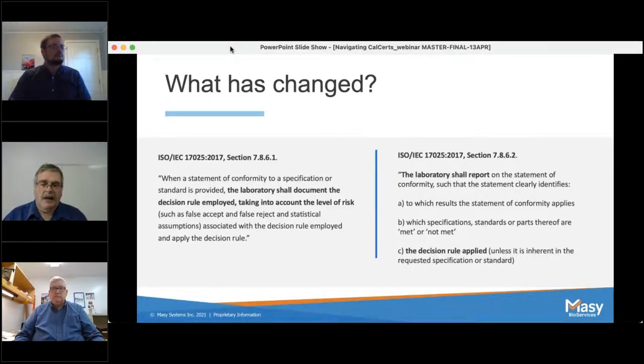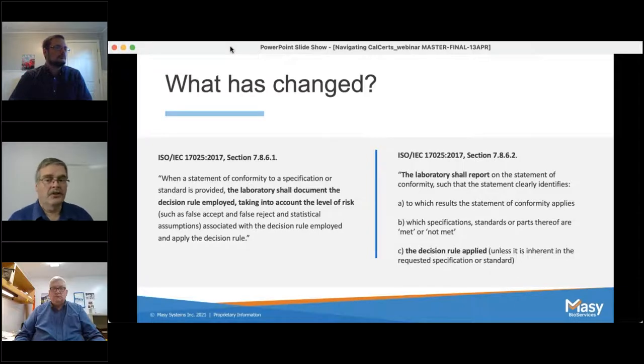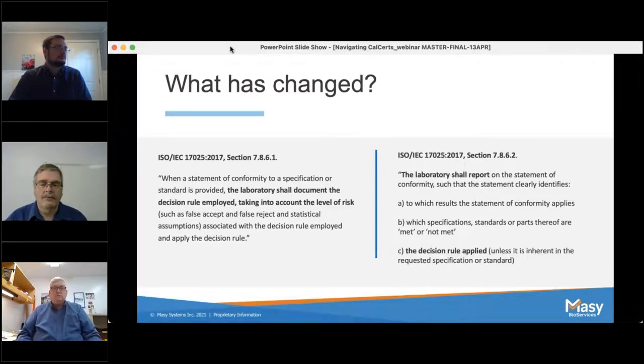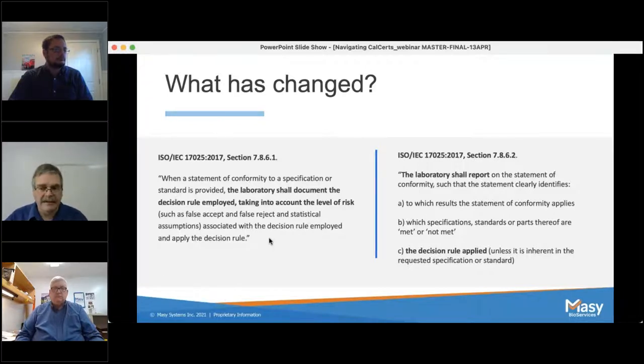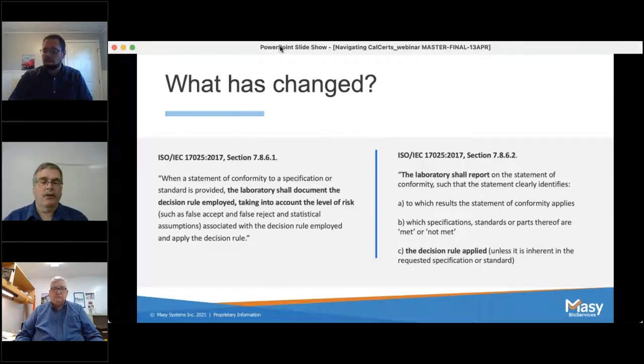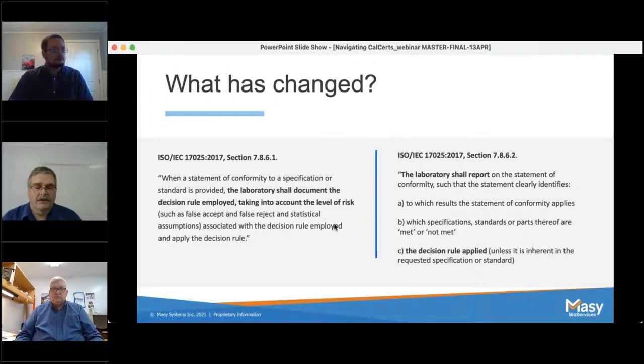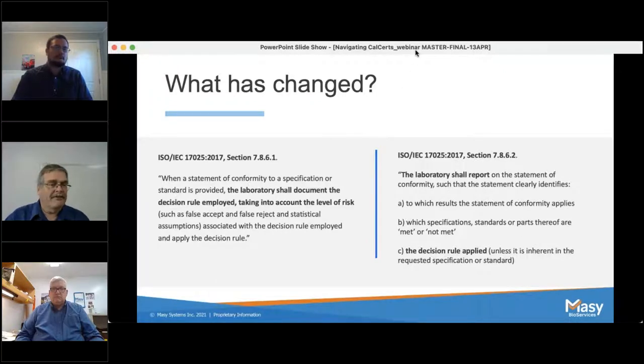So it went from a single sentence in the 2005 standard to referencing this decision rule in four different sections within the 2017 standard. These authors really wanted to drive home what they were expecting calibration and testing labs to do — to really step up their game. So again, what is the decision rule? It's defined as a rule that describes how measurement uncertainty is taken into account when determining pass or fail, in or out of tolerance. That begs the question: what is measurement uncertainty? To answer that, I'll now turn things over to Jeremy Kraft.